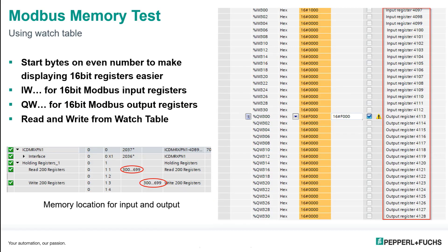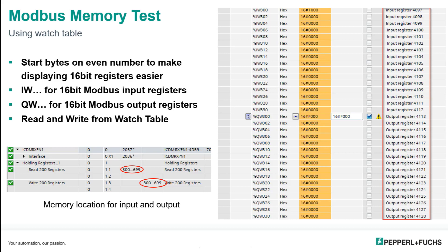And lastly is let's do a test. I don't need any logic in the PLC to make this test. I'm going to simply use my watch table. So IW300, IW330 will contain the 16-bit Modbus registers for inputs. And then QW300 to QW330 will contain 16 Modbus registers for outputs. That's all there is to it. Just remember to right click and force the outputs on for the test.